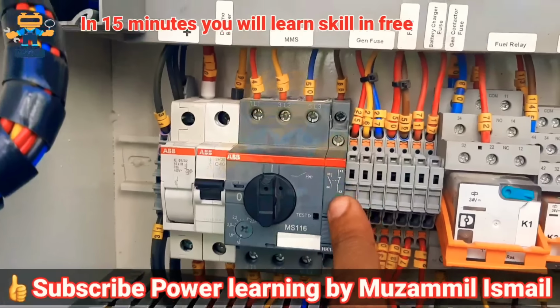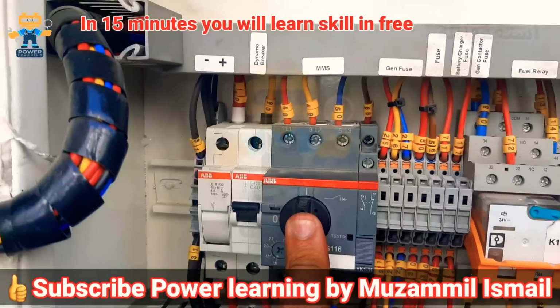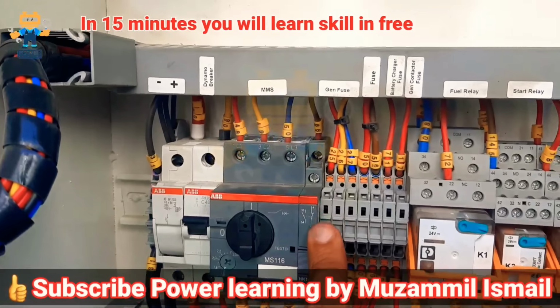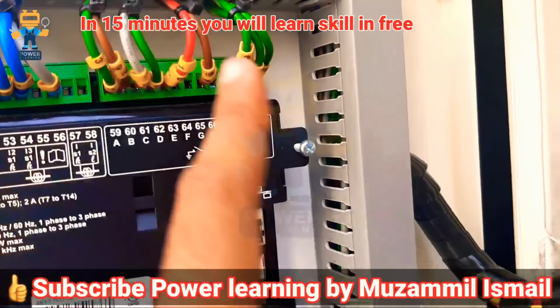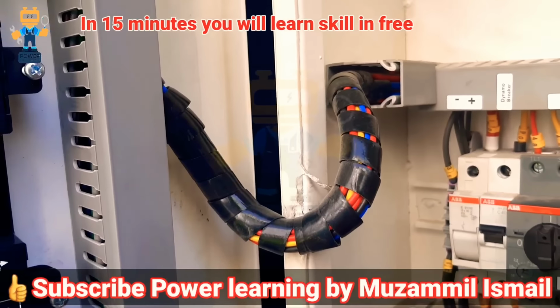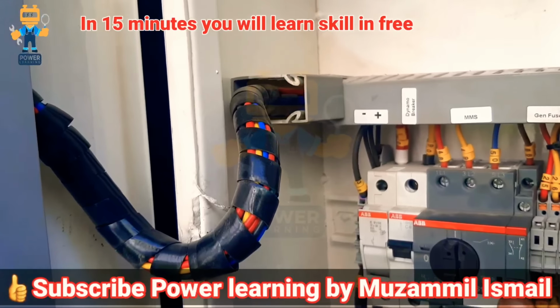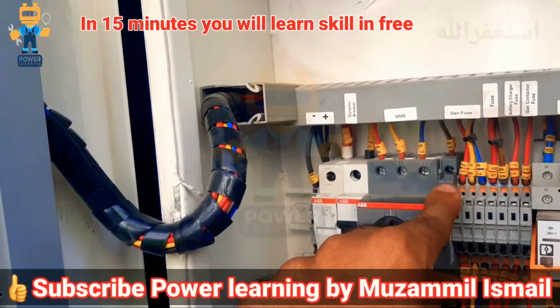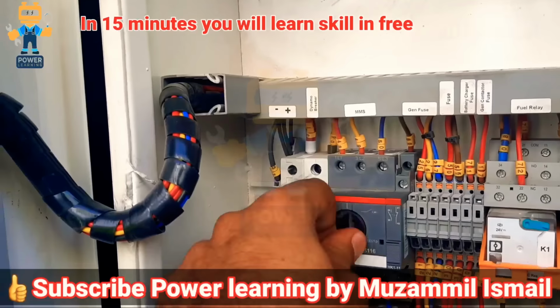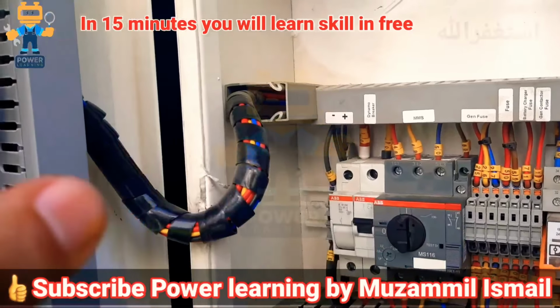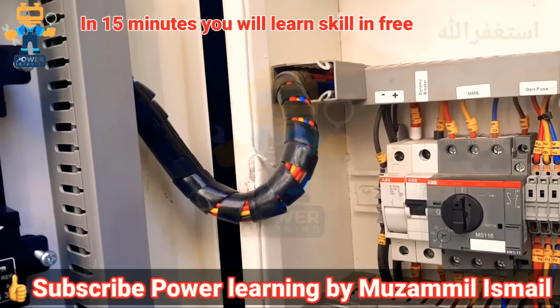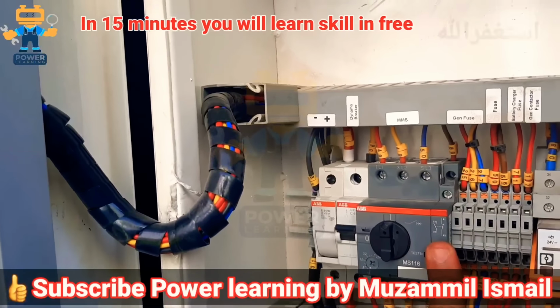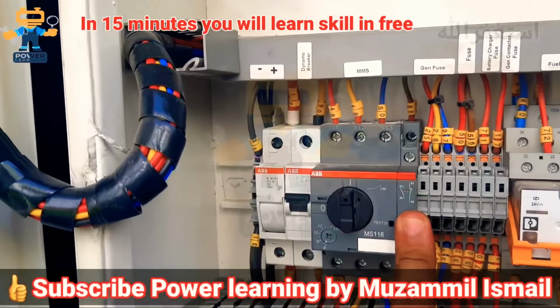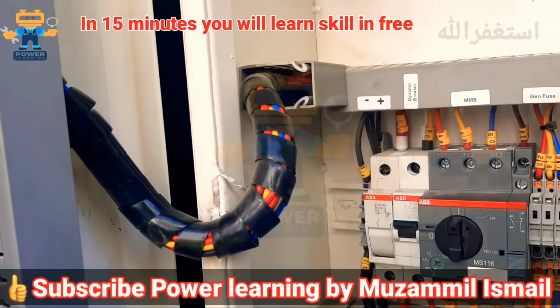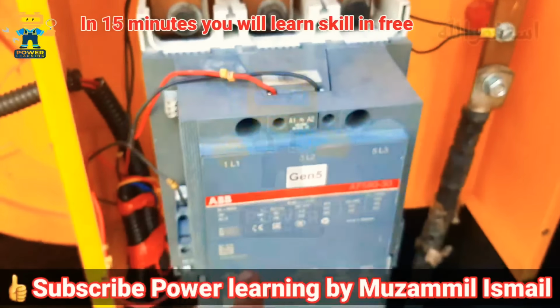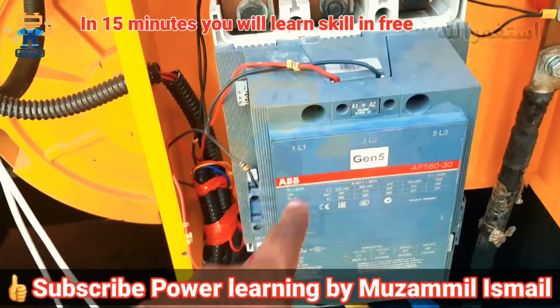After that, this is the auxiliary contact which works with this breaker. This auxiliary is giving a digital input to our controller. If this breaker is tripped, it will show bus supply trip. This is for bus supply sensing. The controller will show the status that bus supply is tripped, so our module will know and immediately open our main contactor. So this is the protection.